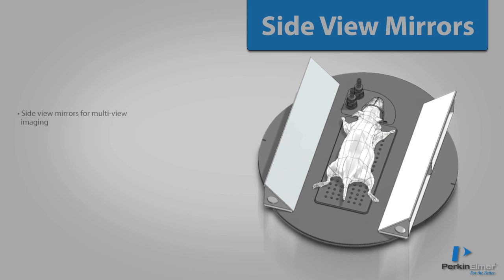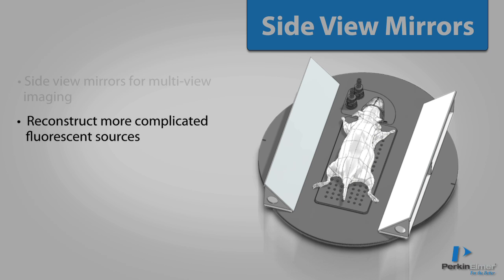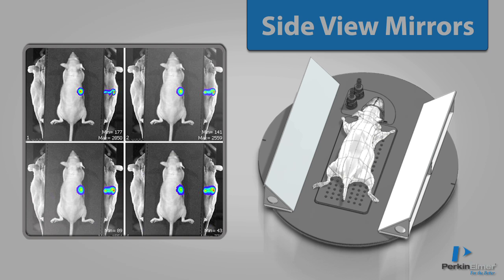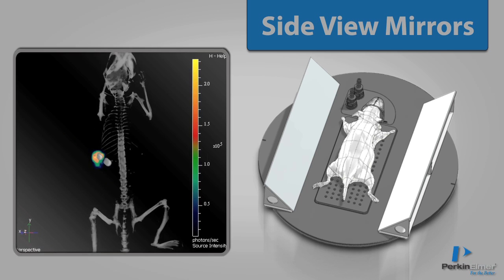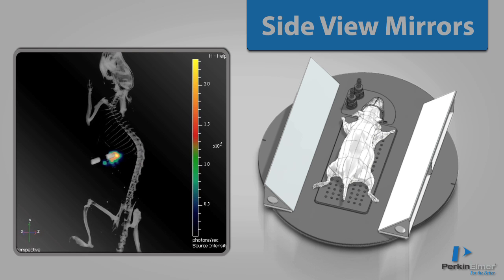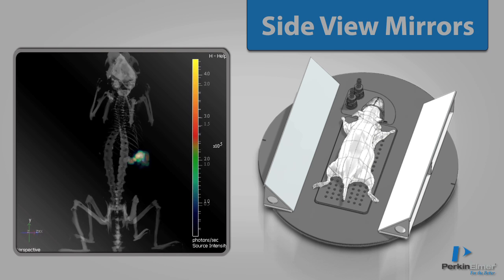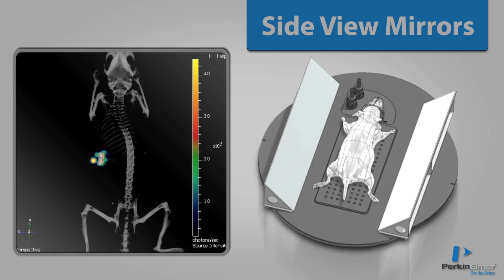Side-view mirrors for multi-view imaging are available with all of Perkin Elmer's IVIS systems. The mirrors help with reconstructing more complicated fluorescent sources, as with this example where two fluorescent sources are located directly on top of one another. With a single view, only one source can be imaged and reconstructed, but with the help of mirrors, the IVIS system is able to discern and localize both sources in the reconstruction.